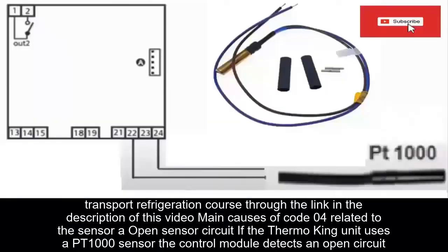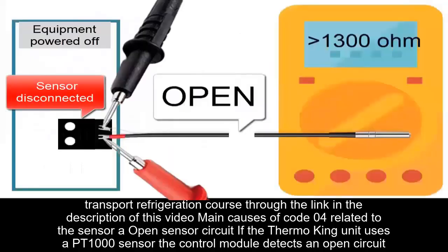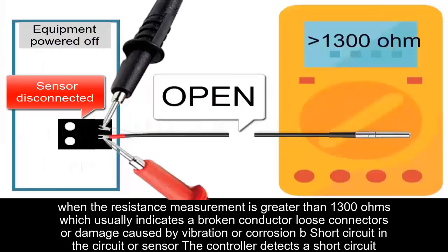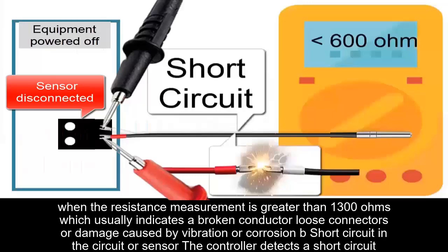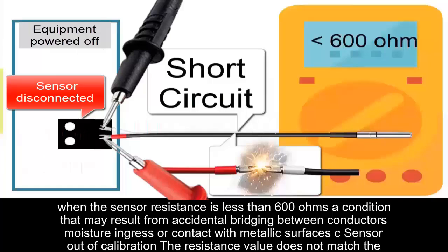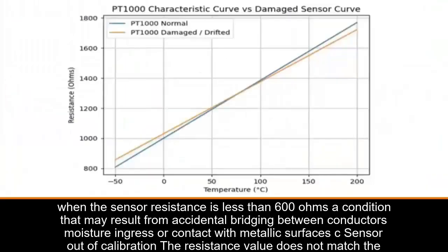Main causes of Code 04 related to the sensor. First, open sensor circuit. If the Thermo King unit uses a PT1000 sensor, the control module detects an open circuit when the resistance measurement is greater than 1300 ohms, which usually indicates a broken conductor, loose connectors, or damage caused by vibration or corrosion. Second, short circuit in the circuit or sensor. The controller detects a short circuit when the sensor resistance is less than 600 ohms, a condition that may result from accidental bridging between conductors, moisture ingress, or contact with metallic surfaces.